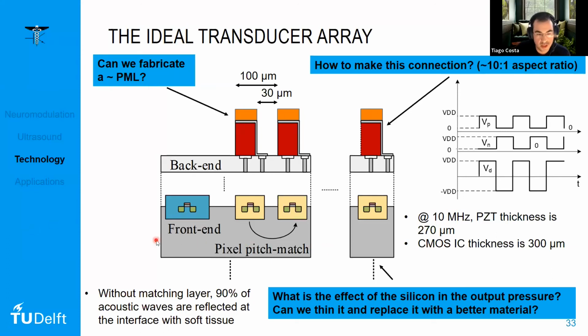That's a very good question. That was actually also one of the reasons I used the epoxy. My first reason to use the epoxy was that one, and then I realized it's also a nice way to have support for the top metal. It is possible that for very high voltages the piezo might even delaminate or break. But these materials are normally able to withstand hundreds of volts, and according to the required pressures, 20 to 30 volts might be enough. So it might not be a problem, but that needs to be properly simulated to see if there are acute problems or long-term problems.